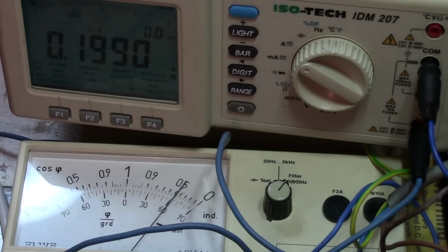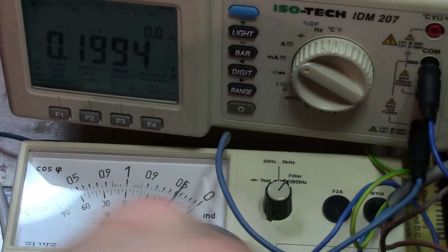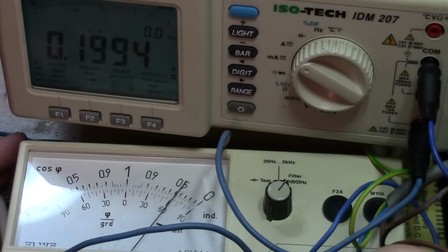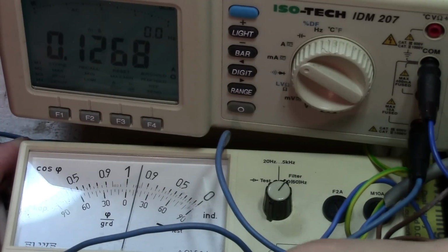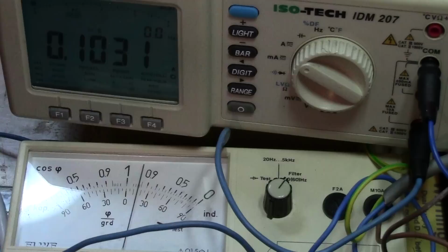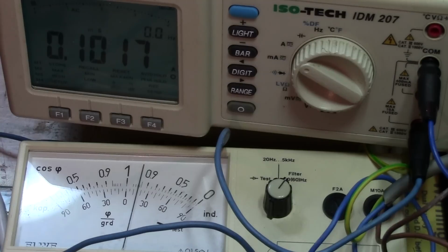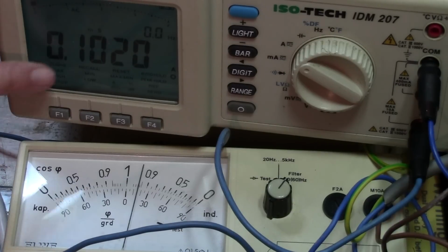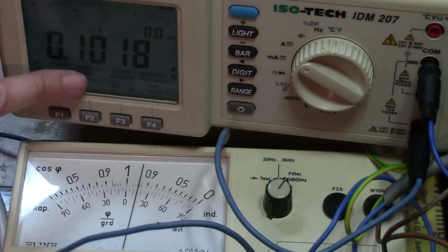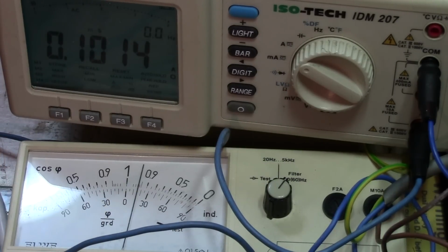Right. So we've now got two capacitors, and again I will now join it in. So we've got 200 microfarads, and you'll see what happens to the meter. We got down to 140 milliamps if I remember rightly, and we are very close to being, you know, what would actually be considered really quite good for power factor correction. And you can see from 140 milliamps we're down to pretty much 100, so we're drawing less current. Same voltage going in, so we're just drawing less current.